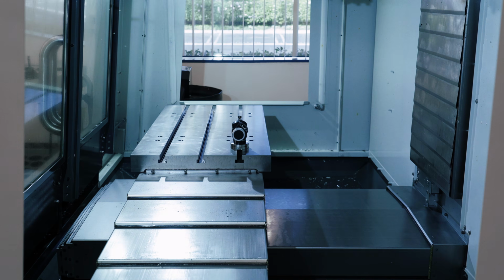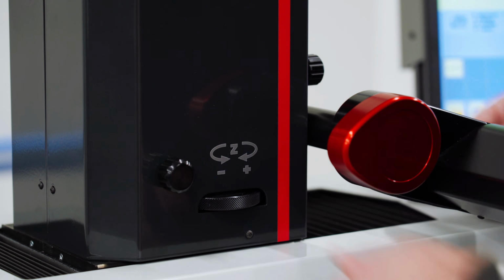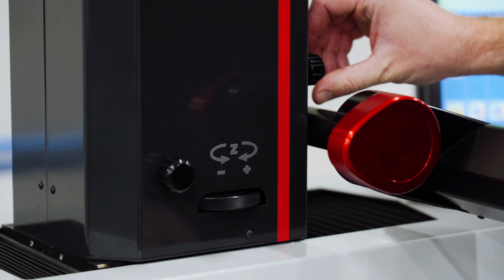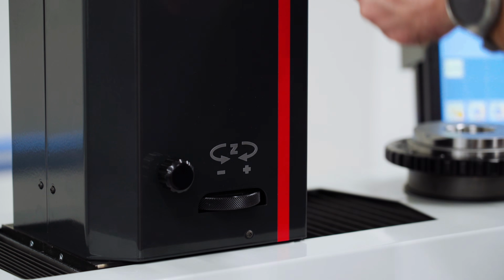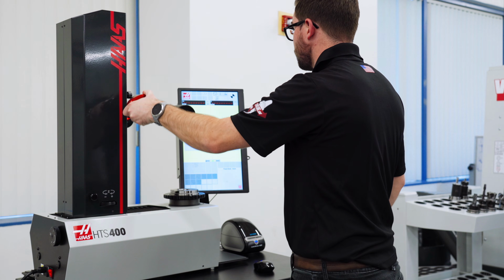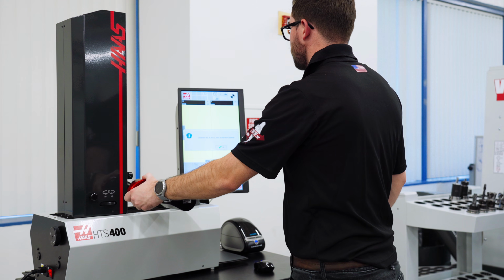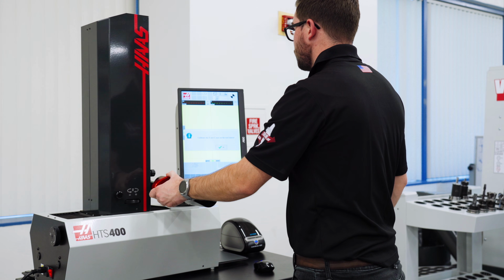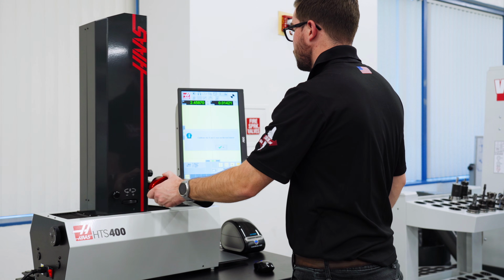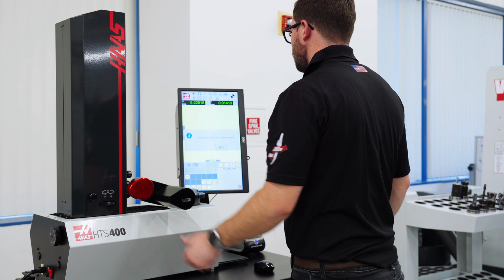Release the lock on each axis and move the lens up and down and side to side until the red flashing lines in the axes readouts turn green. It is important that you only use the red handle to make these movements and never touch the lens. Once finished, you can close the calibration window, and if you haven't changed anything in the time since it was last shut down, you are good to use the presetter and measure tools.